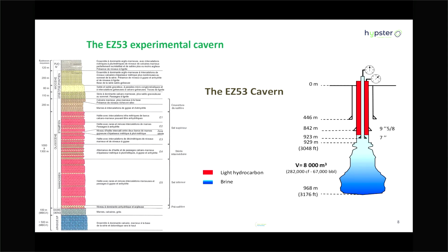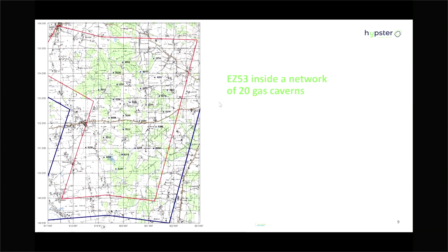It was leached 50 years ago, and we carried out a new measurement of the volume of the cavern, and the volume change is 20 cubic meters in 50 years. So this cavern is quite stable, I would say. The sensitive part of this cavern for the tightness test is the shoe of the casing. In this place, in fact, you have 20 bigger salt caverns, not at the same level, up to 1,400 meters, which are used for natural gas storage, and the volume of these caverns is between 300,000 cubic meters and 500,000 cubic meters.